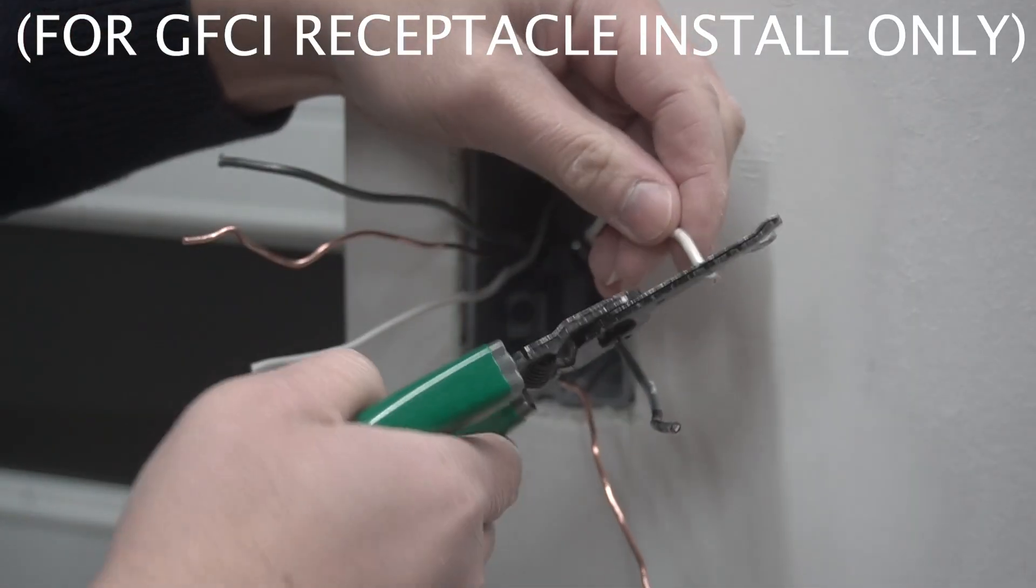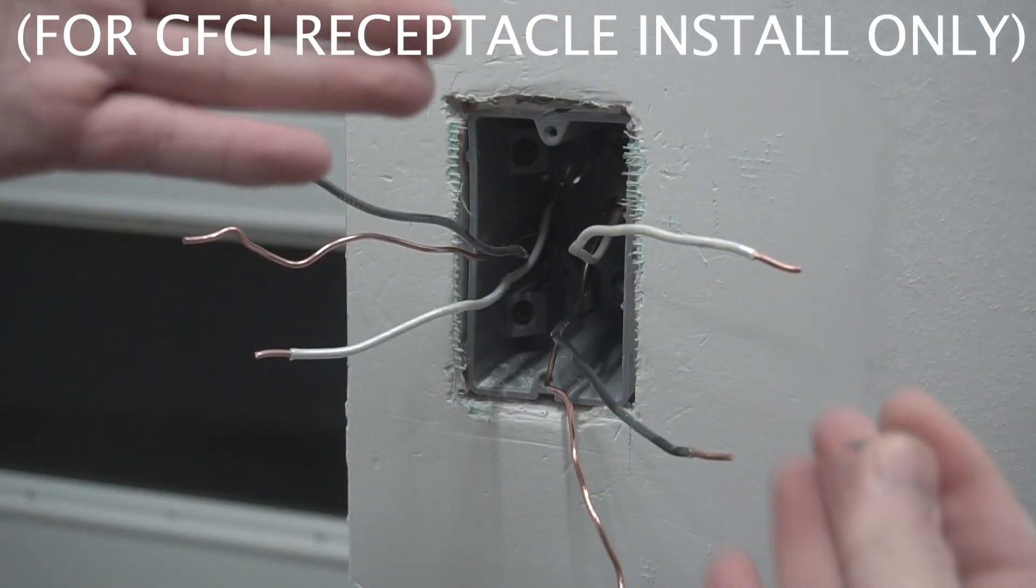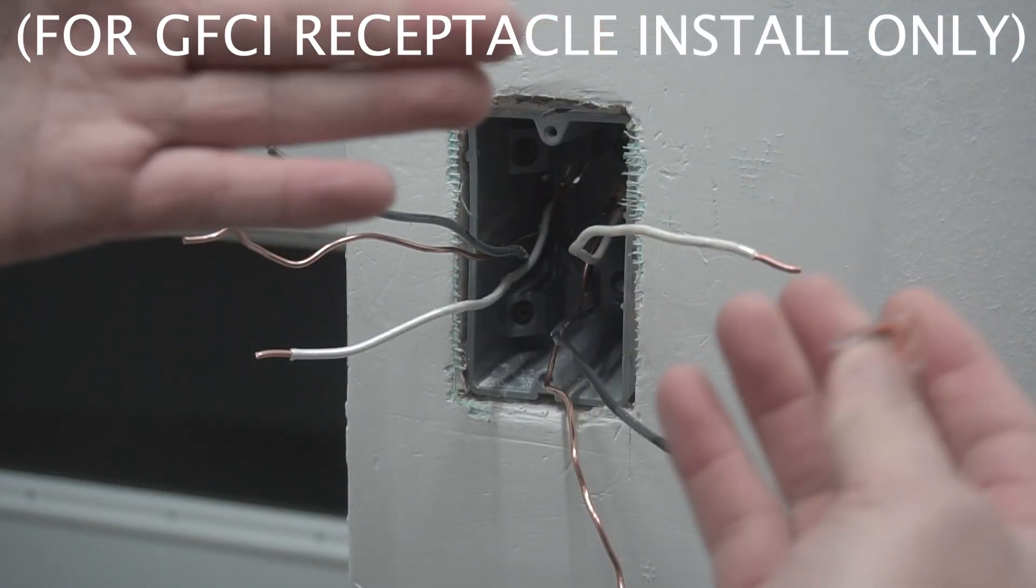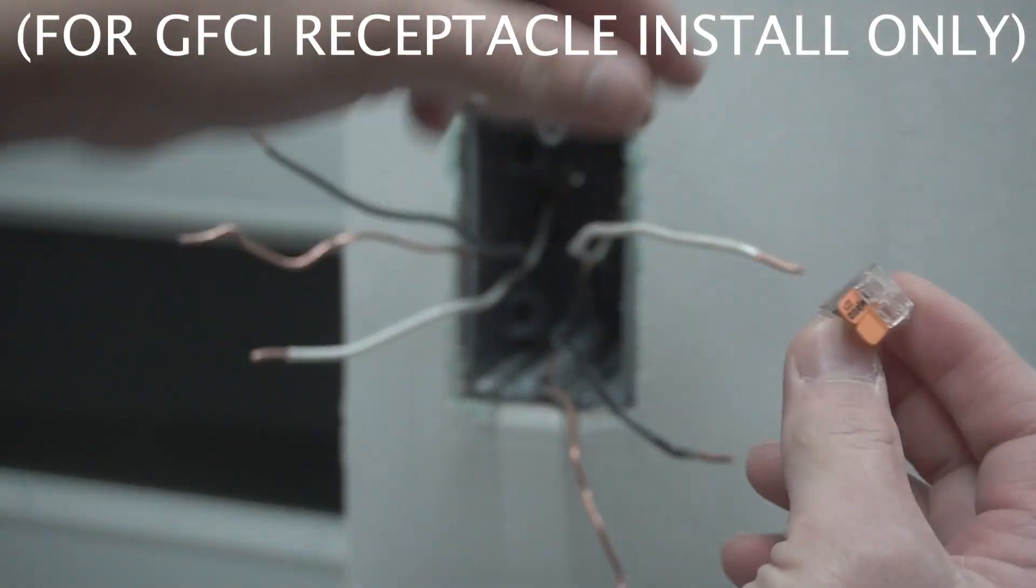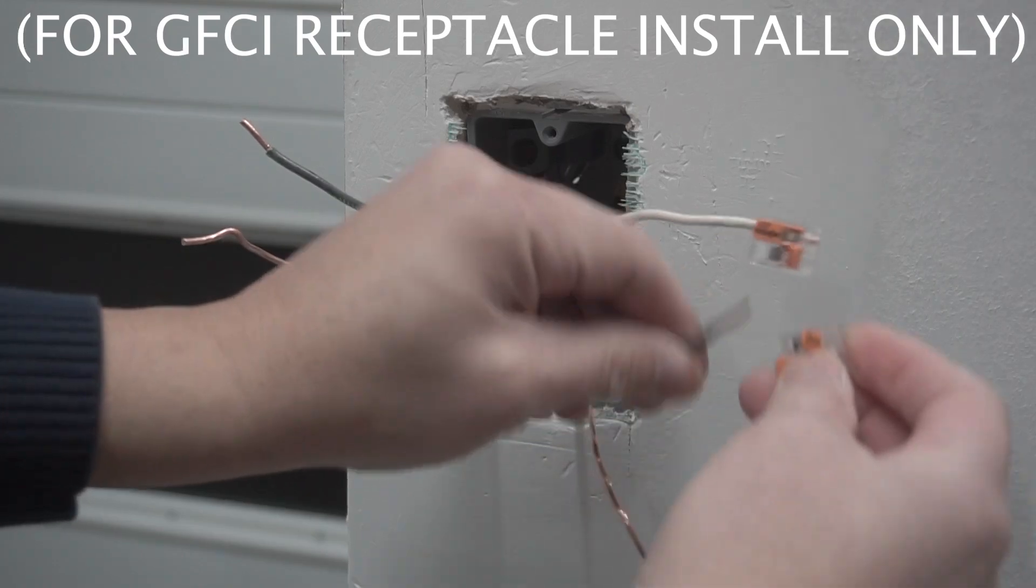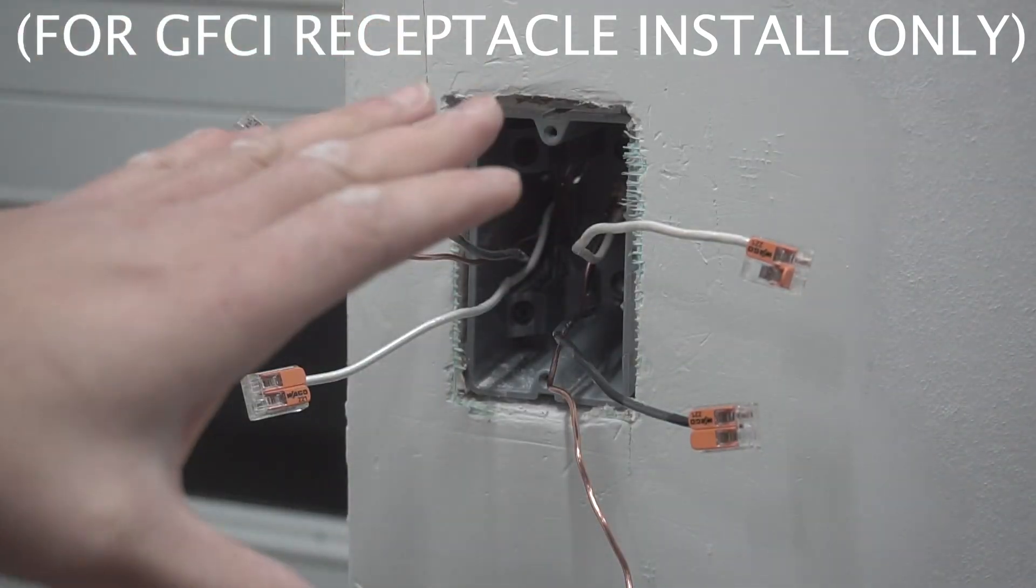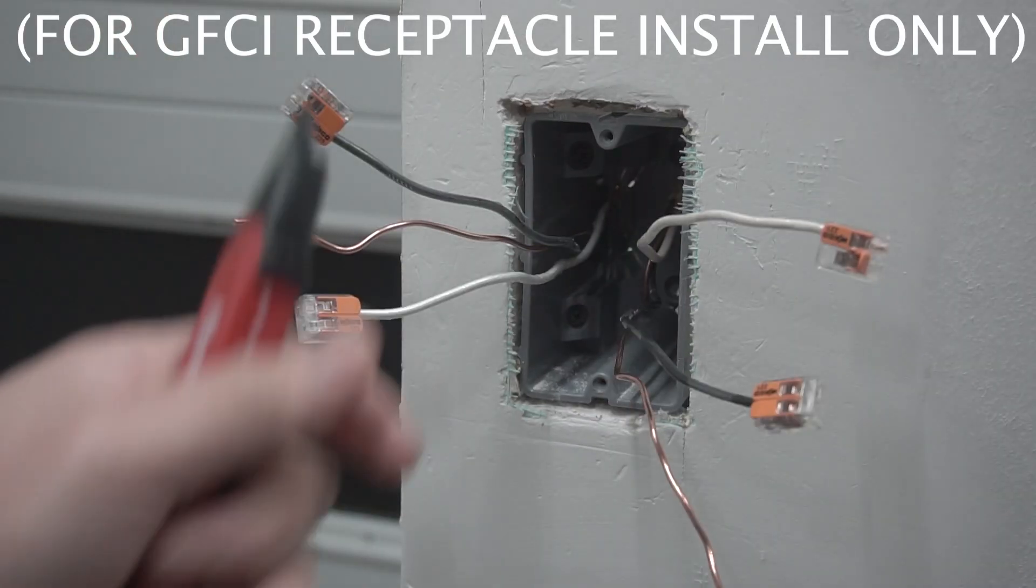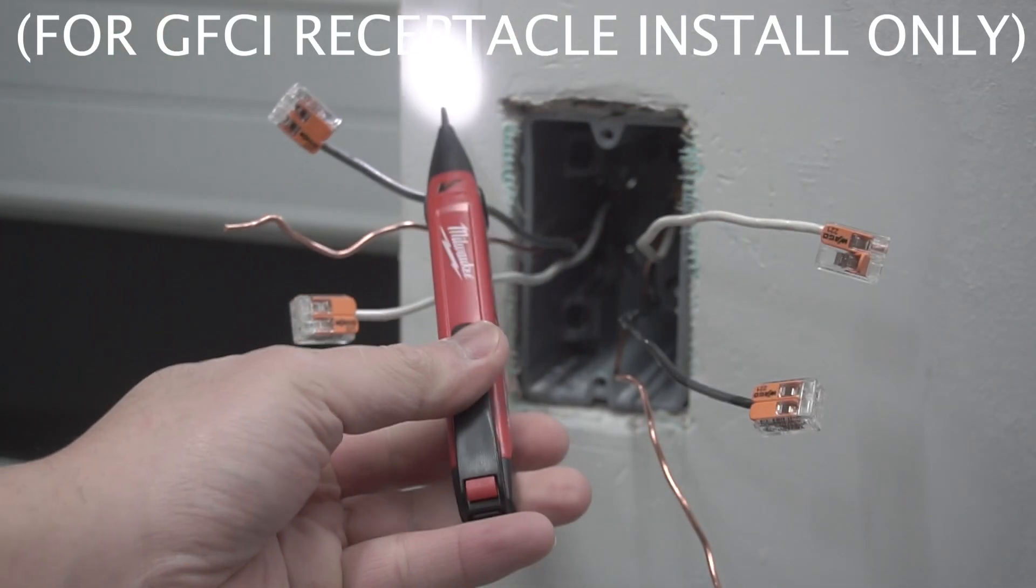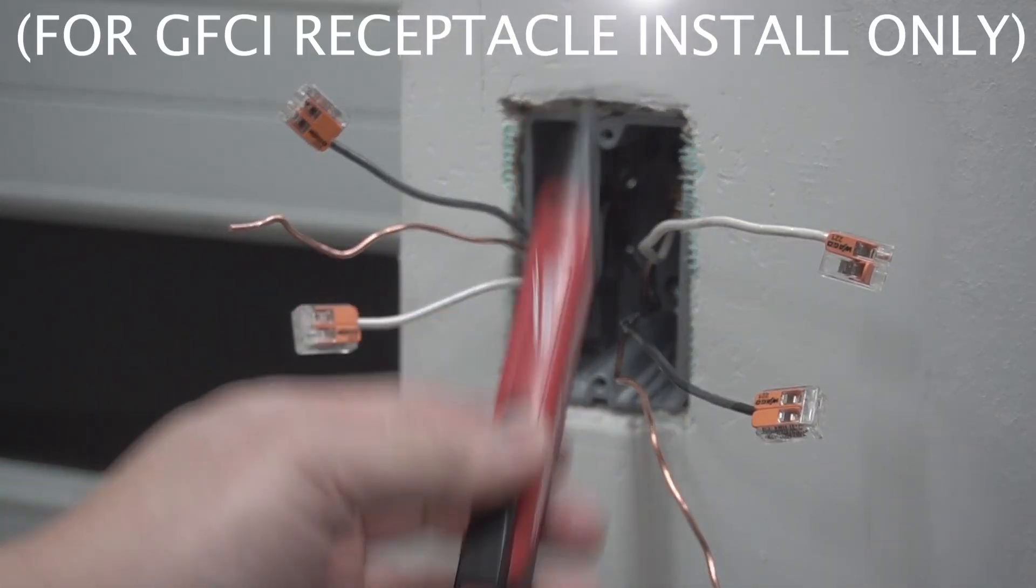So cut off each end like this. We're going to strip the 12 gauge. You can use any connectors that you want to cap these off. You can use a wire nut or what I like to use are these Wagos. They're super easy. Lift the lever and just close it up just like that. I'm only going to be capping the neutral and the hot.